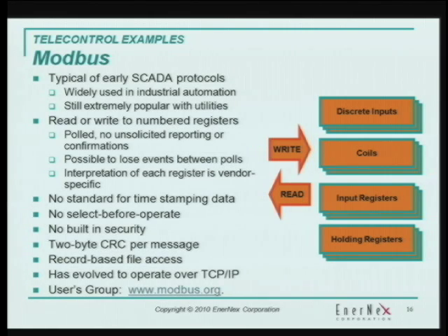An early protocol still around today, called Modbus, was very widely used in industrial automation, with the basic concept of being able to set a variable and get a variable. It was patterned after physical manifestations, so in the terminology you'll see registers referred to as coil registers, input registers, or holding registers. It still had mapping to the physicality of the devices, so it was still very tightly coupled.